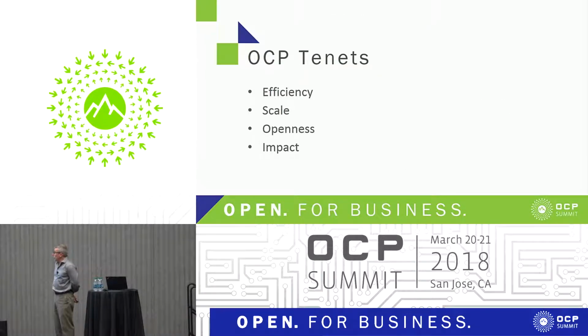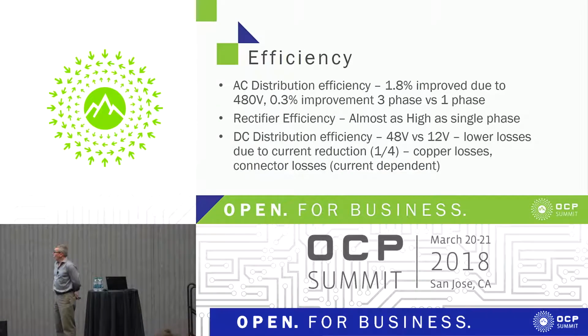In terms of the OCP tenets, we've tried to address each of these: efficiency, scale, openness, and impact. From the standpoint of efficiency, the AC distribution efficiency comes into play here, and we estimate that there's probably a 1 to 2% improvement over a single-phase distribution system in total in the AC distribution, which offsets the fact that a 3-phase rectifier is inherently just a little bit less efficient than a single-phase rectifier. The higher input voltage helps, but the 3-phase conversion doesn't work in your favor.